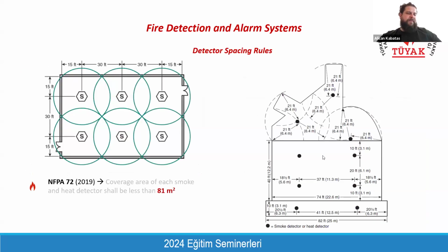This is the spacing rule for the detectors. We have a limitation on the spacing between the detectors, and it should be taken into account because the reflected ceiling plans are prepared by architects on the site, and architects are always changing the location of these fire detection equipment according to the other installations found on the ceiling. But these spacing rules should be taken into account while preparing reflected ceiling plans. Otherwise, when you send the final design to the consultant, you will get comments about it, and they will ask you to make it code compliant.